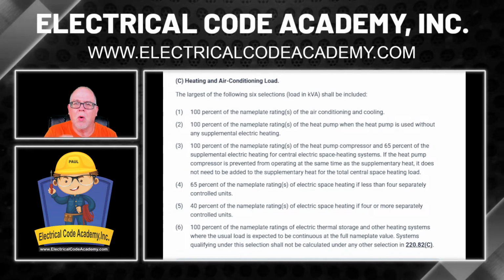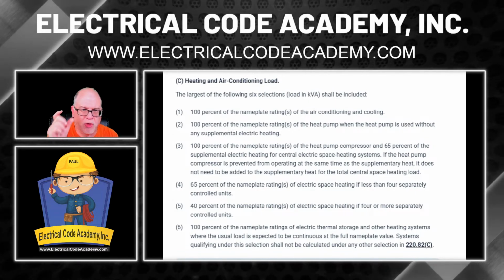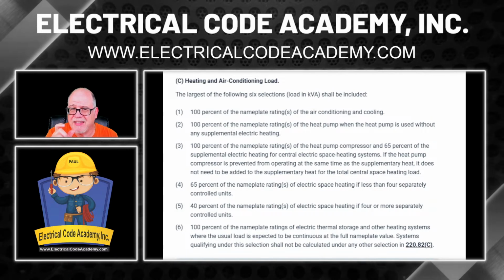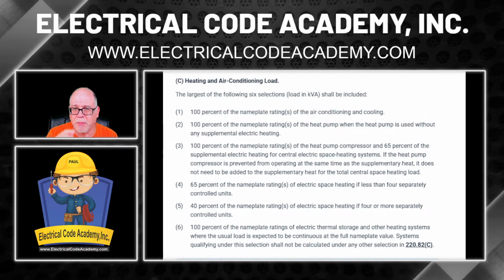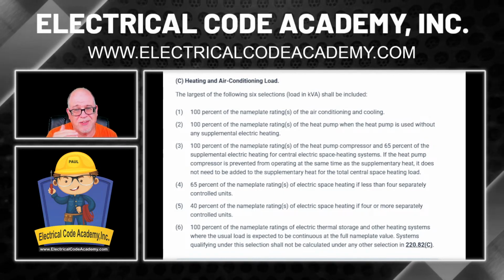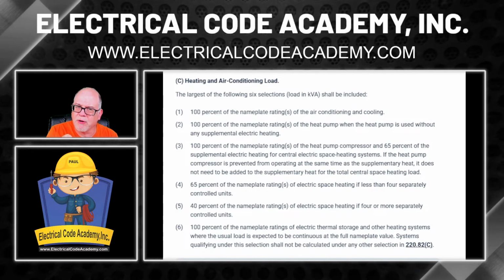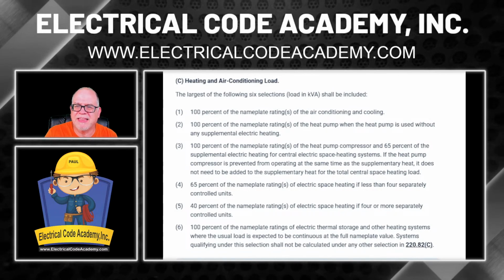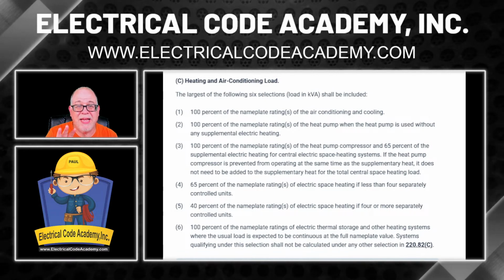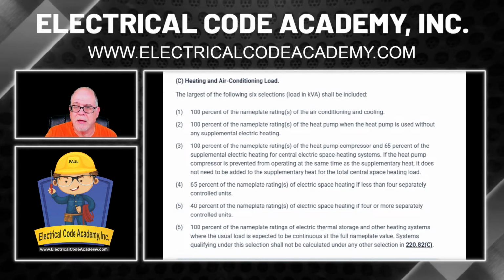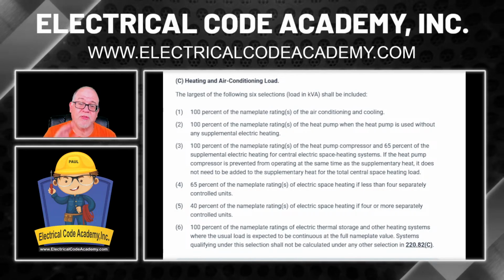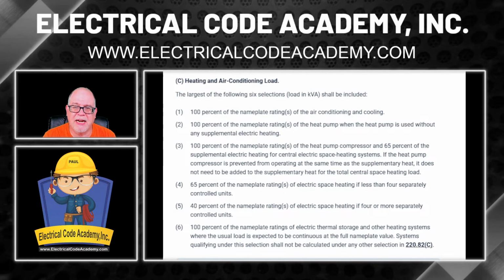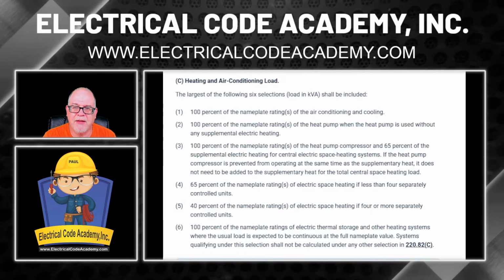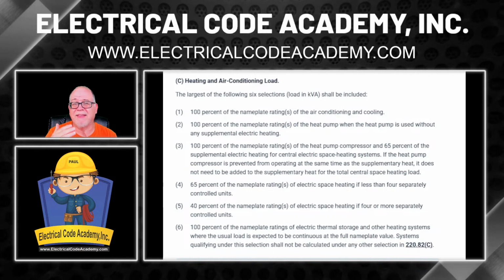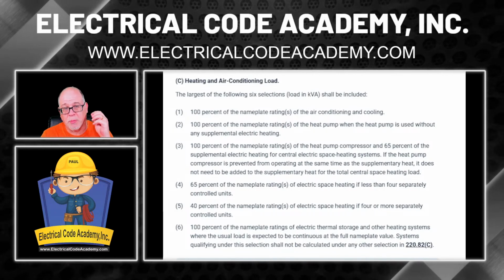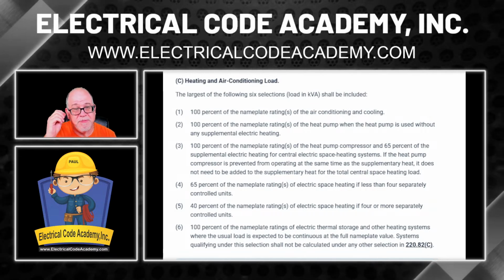So we know that when it comes to the AC, we're going to take its full value at 100%. Now we need to look at the heat. Looking down the list, number 2 is a heat pump. Number 3 is still talking about heat pumps. Number 4 is 65%, but that's electric space heating when you have less than 4. We had 6, remember? So then we have number 5, which says 40% of the nameplate rating of electric space heating if there are 4 or more separately controlled units. We had 6, so obviously we're going to be comparing number 1 for AC versus number 5 for the heat.